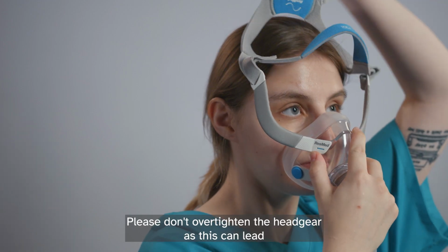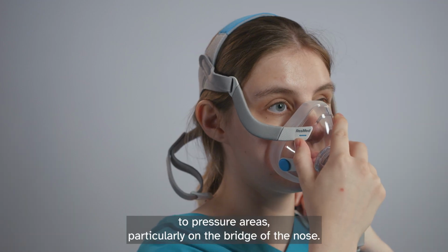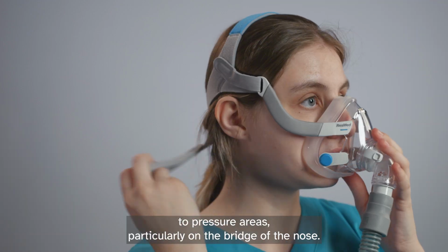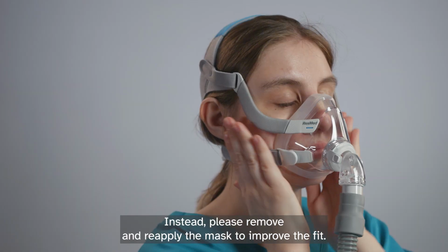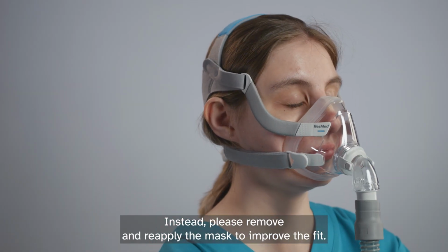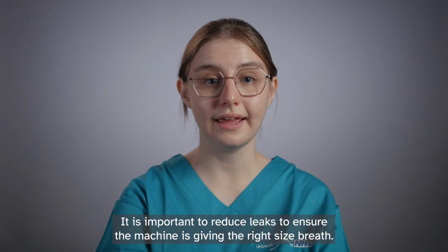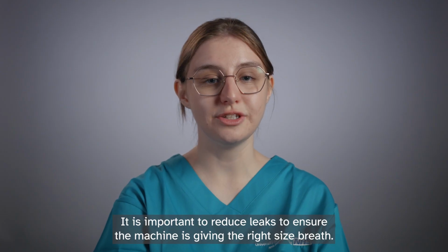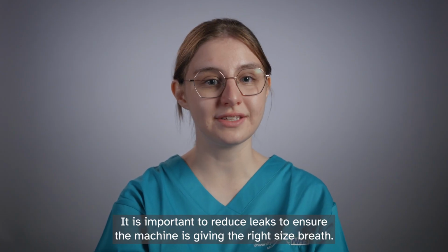Please don't over-tighten the headgear, as this can lead to pressure areas, particularly on the bridge of the nose. Instead, please remove and reapply the mask to improve the fit. It is important to reduce leaks to ensure the machine is giving the right size breath.